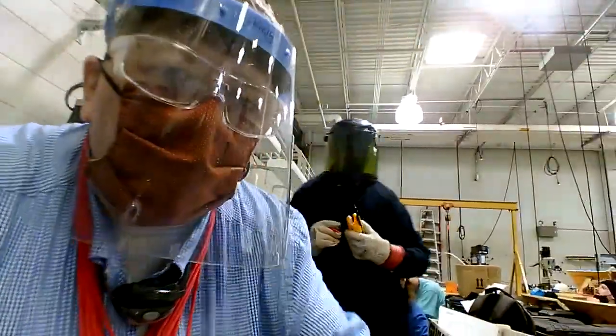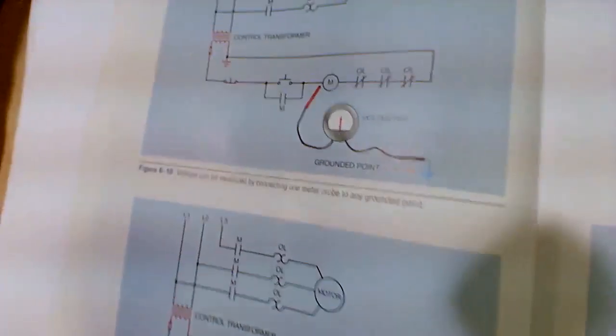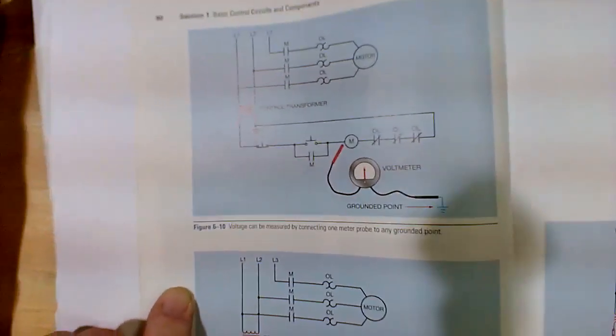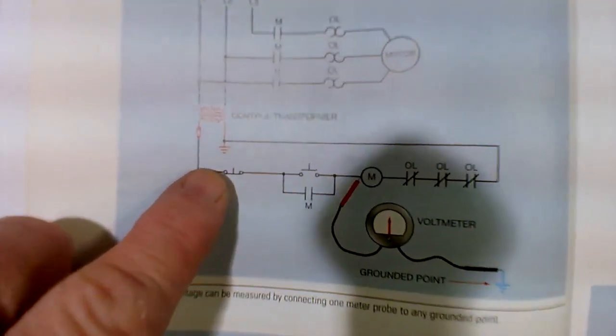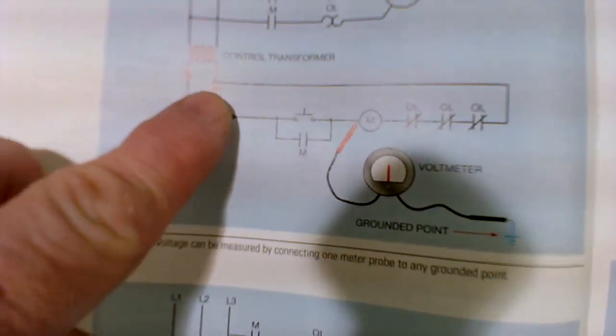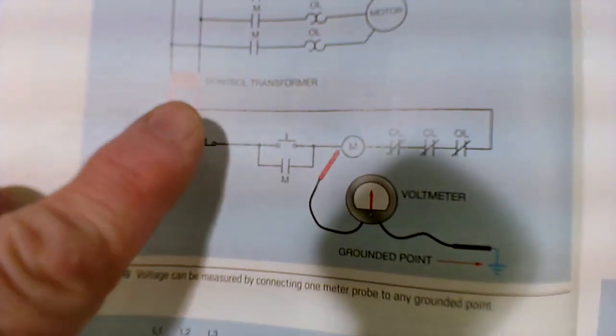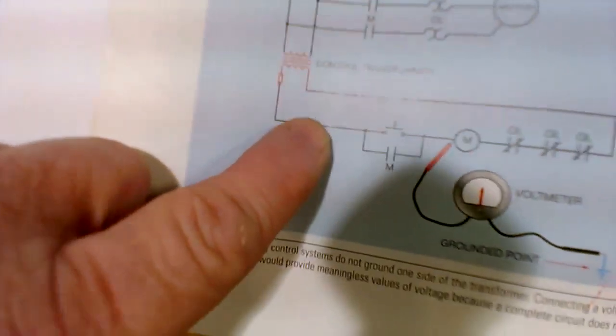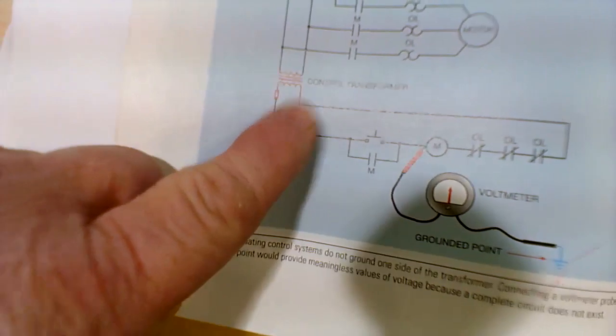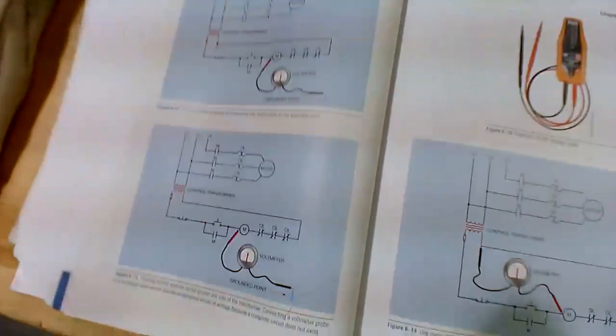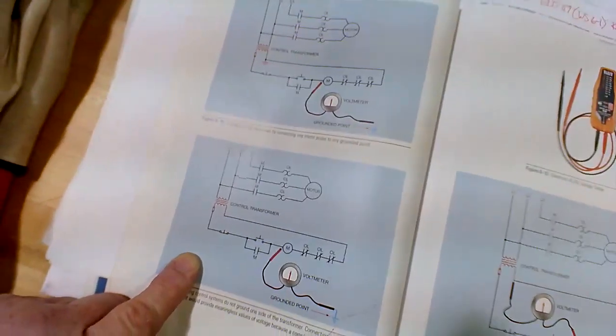So I'm going to just show you here with the webcam a picture in the book of a transformer that's not grounded on the secondary. This one here is not. This one is grounded on the secondary on the neutral, like you've been doing on your labs. That's considered a grounded secondary. One that doesn't have a ground on the secondary, you don't see the ground symbol there, is called floating. There's a difference in how you have to use the meter if it's grounded or floating to get a correct reading. So I'm moving the camera again.